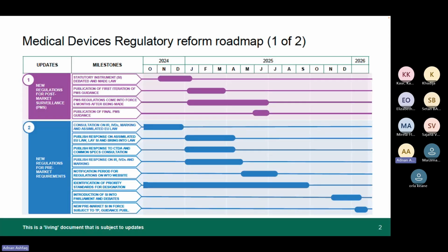So the roadmap is that the regulatory reform is changing. There are regulatory changes in the UK framework. This is the current timeline. It's a living document, but it was released in December last year, so it's not very old. As it stands, we've got a timeline of around June 25 for regulations for post-market surveillance to come into effect. The draft for post-market surveillance came out late last year, and pre-market requirements for new regulations will be formalized at some point in 2026. At the moment this is being drafted, and there have been lots of surveys taken by the UK government from public consultation on what that needs to look like. My guess is that it's going to start looking more like the European medical device regulations, but where some severe mistakes have been made within the European regulation, those are something we do not want to repeat.